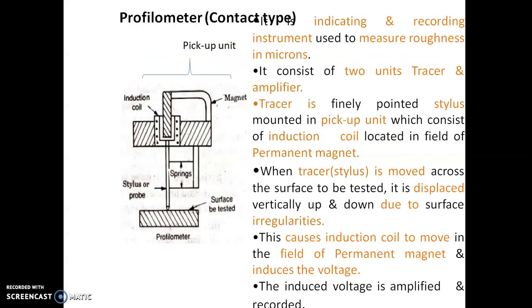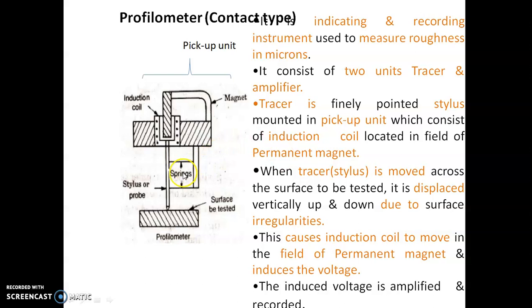All other instruments work based on this principle. The profilometer consists of a permanent magnet and an induction coil along with a stylus probe. When the stylus probe moves over the surface, it induces a voltage which is amplified, converted into an electrical signal, and then converted into a surface roughness measure.